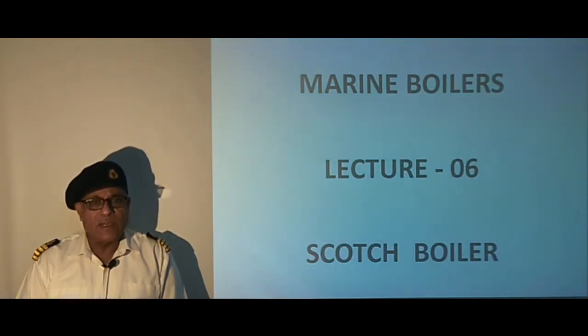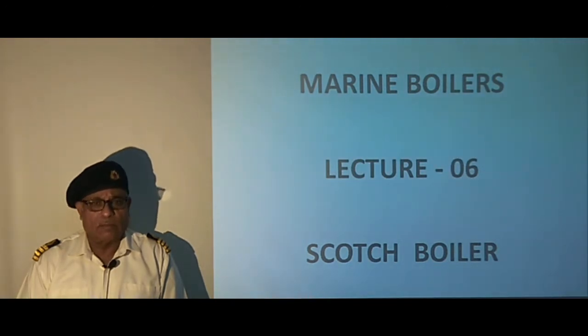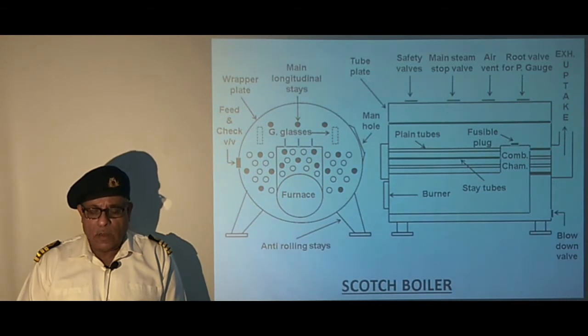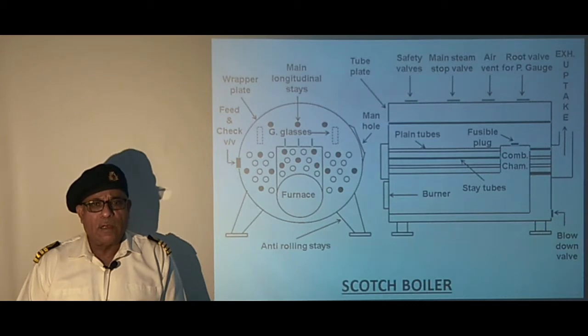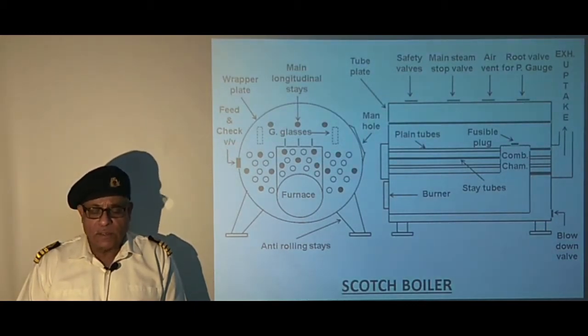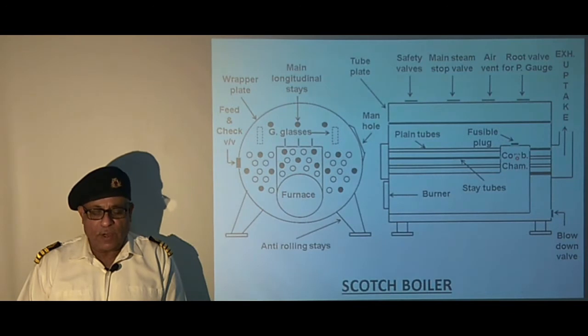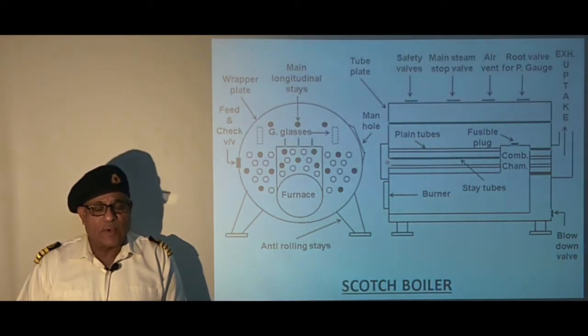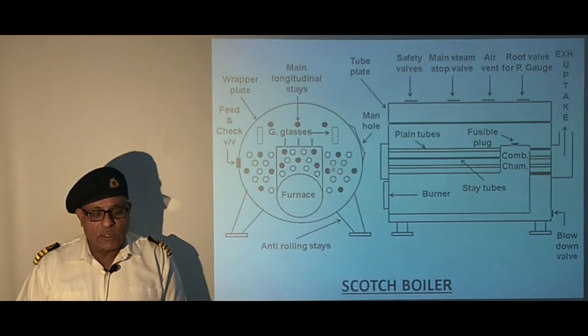In the following slides, we will learn its constructional details and the flow of gases through the boiler. The figure shows a Scotch boiler with single furnace, although other designs had 2 or 3 furnaces depending on boiler size and required evaporation rate. We can see the furnace extended into the combustion chamber, and these are the smoke tubes which bring the flue gases back to the front end, taking a third pass through tubes on the side of the combustion chamber and exhausting at the other end.